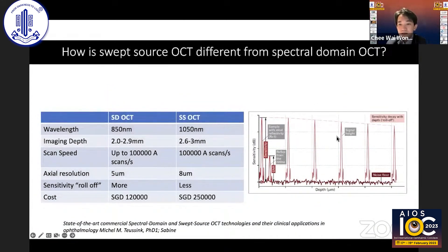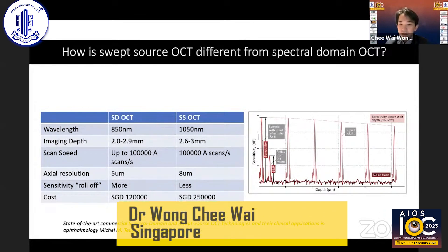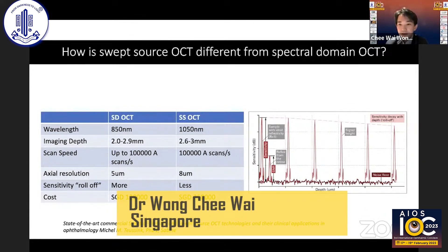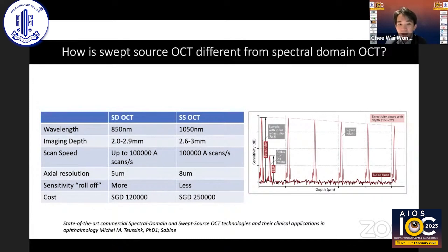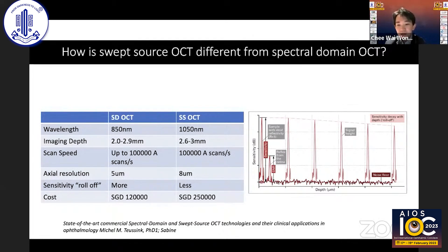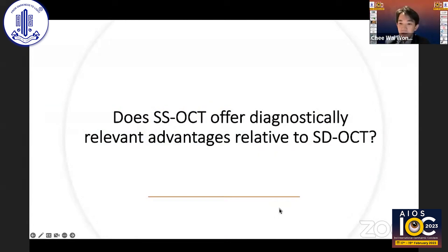The main technical difference is the wavelength employed: 850 nanometers in spectral domain versus a longer 1050 nanometers in swept source. Swept source has slightly greater imaging depth and less sensitivity roll-off. Scan speed is similar between the two; commercially available machines can achieve 100,000 scans per second for both. Axial resolution is actually higher for spectral domain at 5 microns compared to 8 microns in swept source. In terms of cost, swept source is still much more expensive.